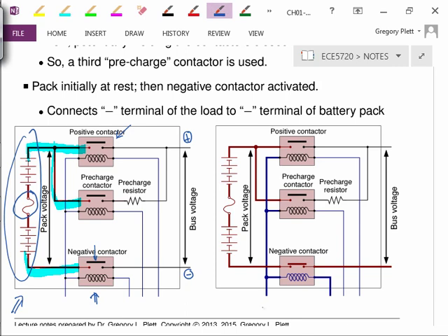You can see this line is now drawn as thick, showing we've connected it, and this line here too. Since the coil is activated, it's drawn blue instead of black, and we show the connection closed. The other contactors are still open — they have power applied to one terminal, but not the other, so the coil is not actually activated.